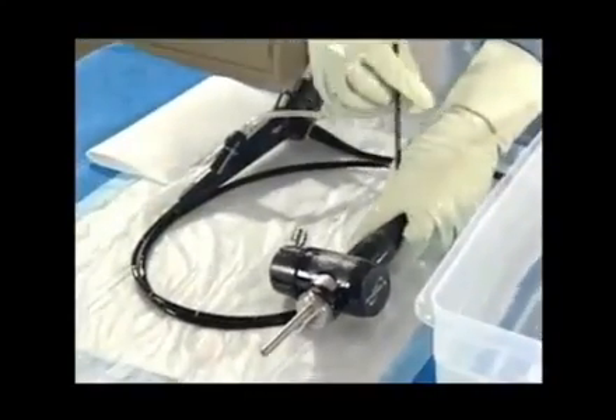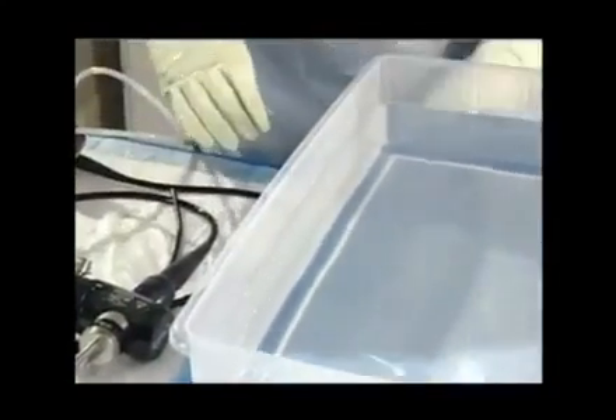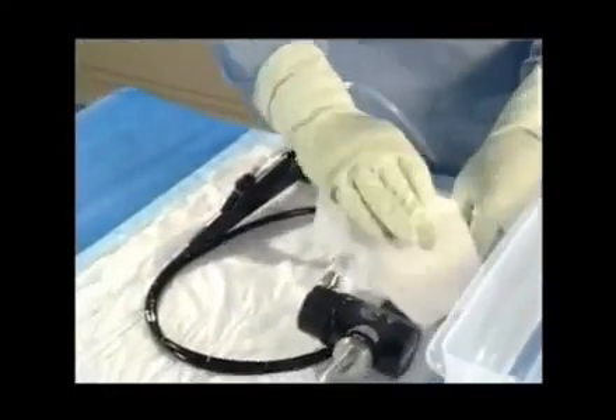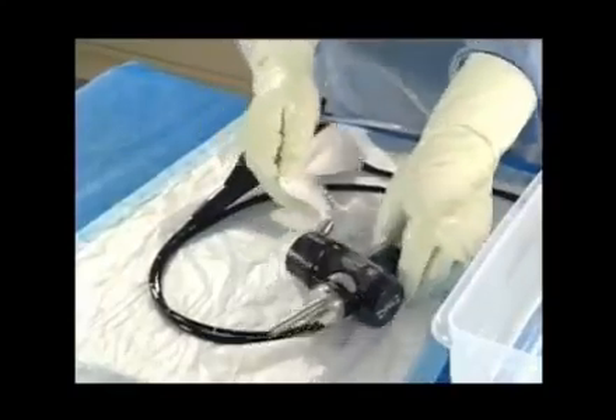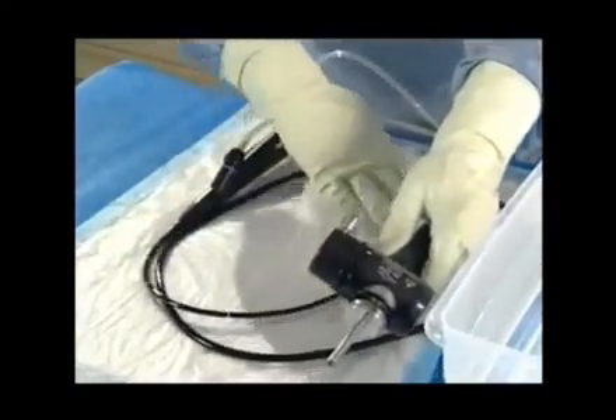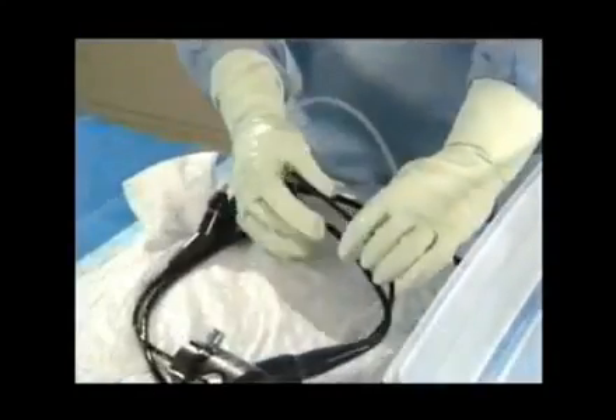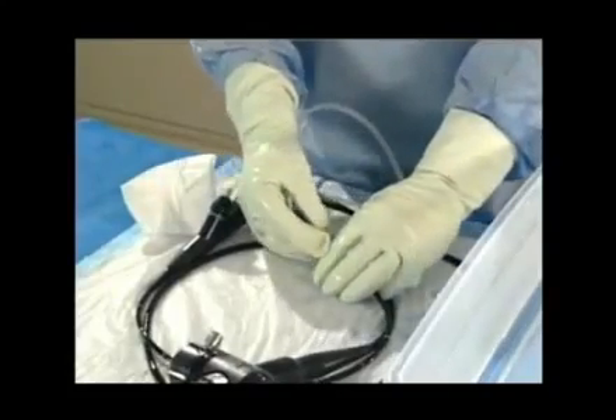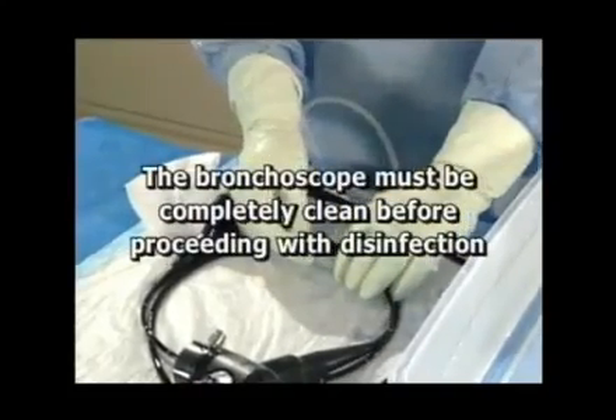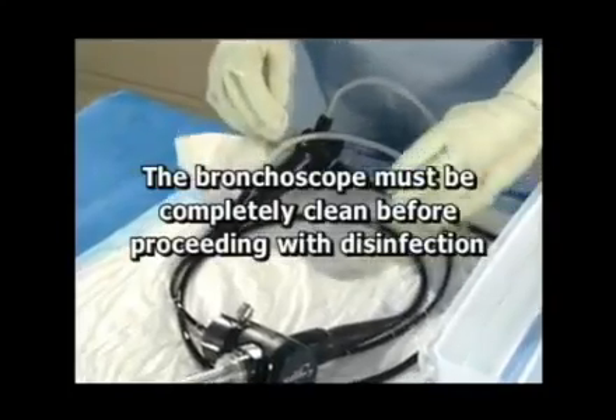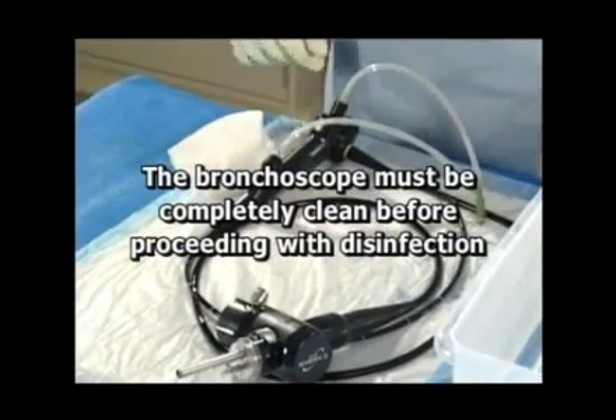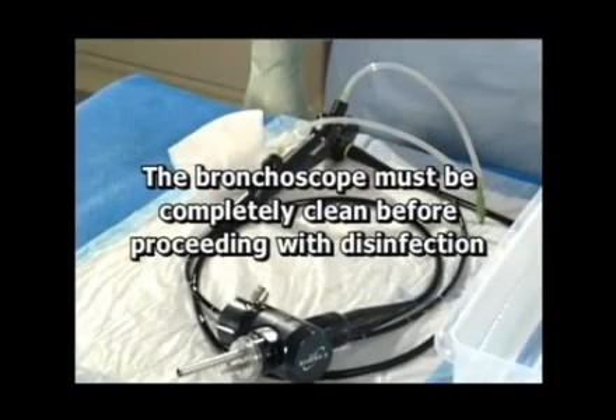Completely remove the bronchoscope and cleaning adapter from the rinse water and place it on a clean, dry cloth. Use a dry, lint-free cloth to dry all external surfaces of both the bronchoscope and the suction cleaning adapter. Visually inspect the bronchoscope and cleaning accessories. If any debris remains, you must repeat the manual cleaning process. The bronchoscope must be completely clean before proceeding with disinfection.